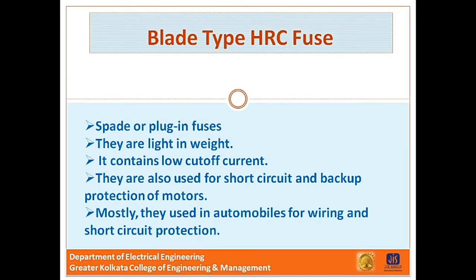Next one is the blade type HRC fuses. Now these fuses are also known as spade or plug-in fuses. This type of fuses comes in plastic body and two metal caps to fit in the socket. They are light in weight and they contain low cutoff current. Mostly they are used in automobiles for wiring and short circuit protection. They are also used for short circuit and backup protection for motors. And they are available in different sizes and shapes with different current rating capacity which is printed on the top.